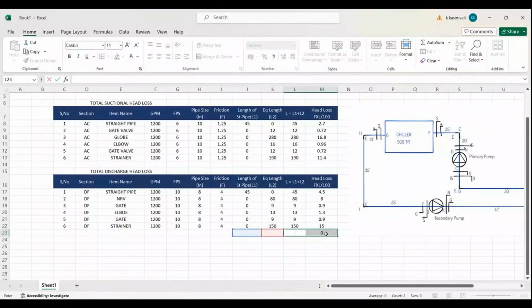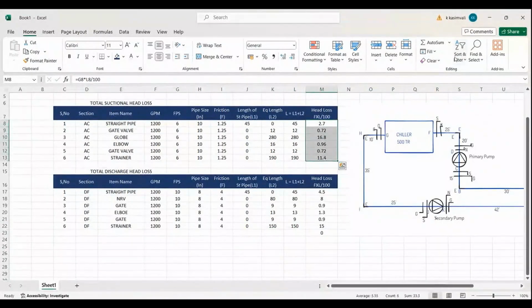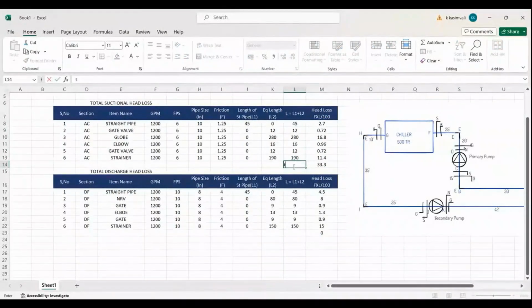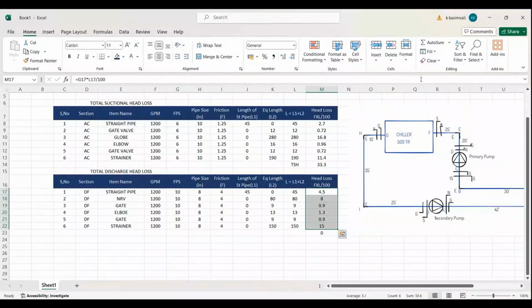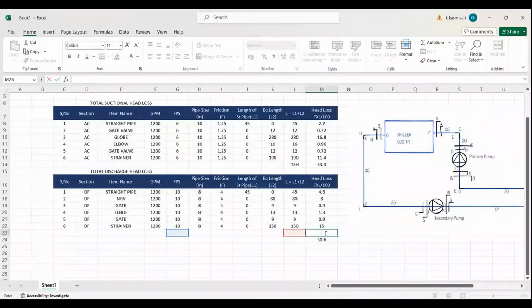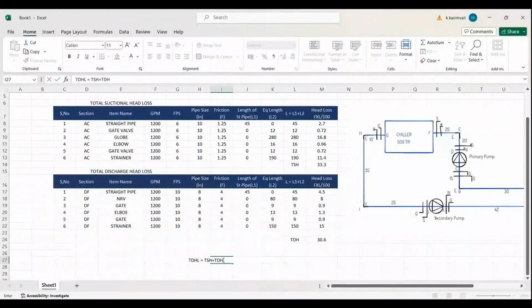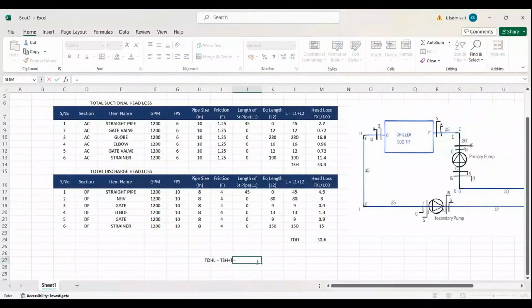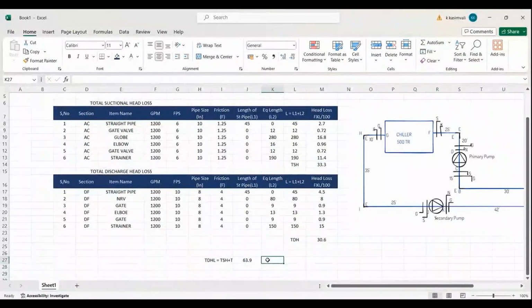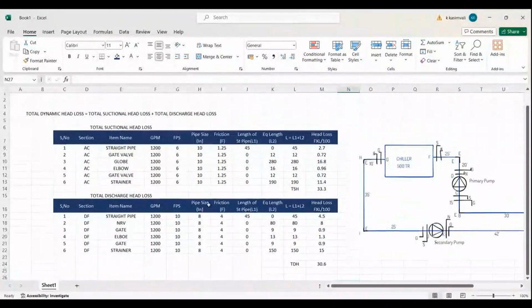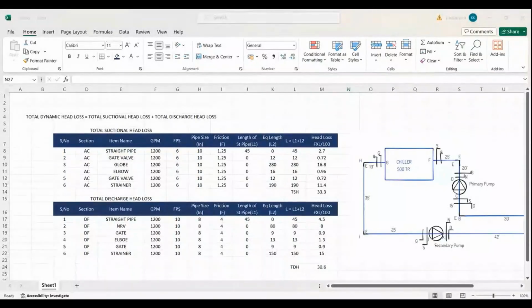After summing these values, you'll get TSH, total suction head loss. After summing these values, you'll get the total discharge head loss. Therefore TDHL equals TSH plus TDH. TSH plus TDH equals this plus this, which is 63.9, approximately 64 feet. 64 feet. Okay, make a note of this fast. Note down these values, tables.